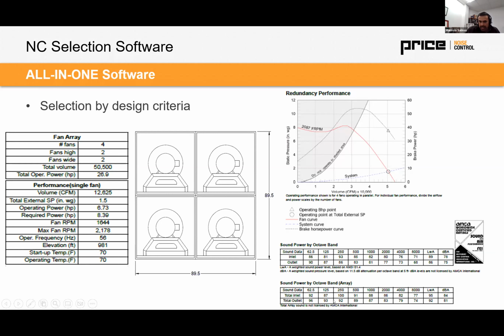They logarithmically added all these numbers, 96, 93, and it's 92 dBA sound power. That's the amount of energy the unit is radiating. Now, the 81 that you see, sound pressure, is how that 92 decibels is heard by the human ear 5 feet away. And I know that because I'm reading this note on top that says they are taking 12 decibels off to simulate 5 feet away.